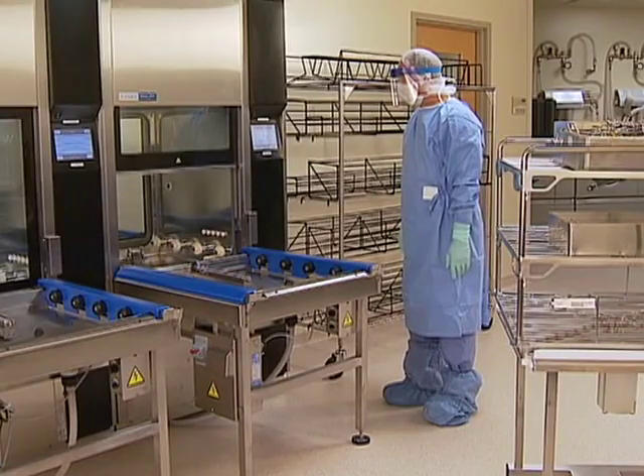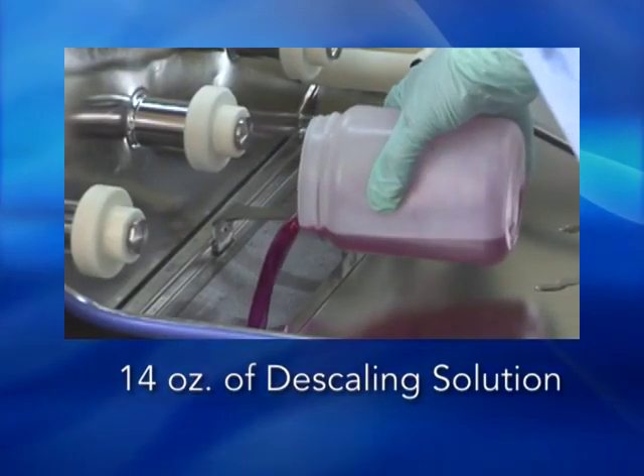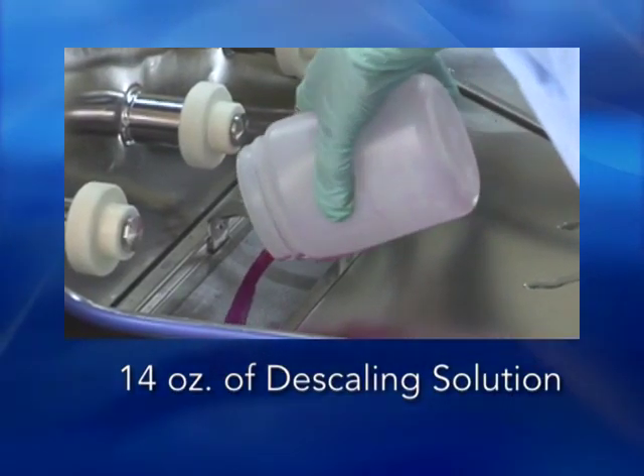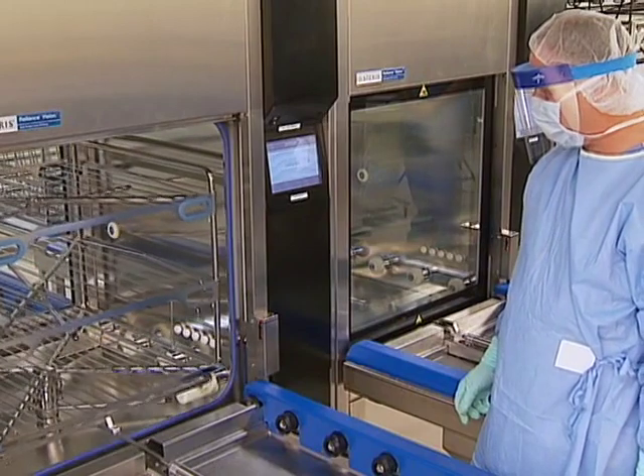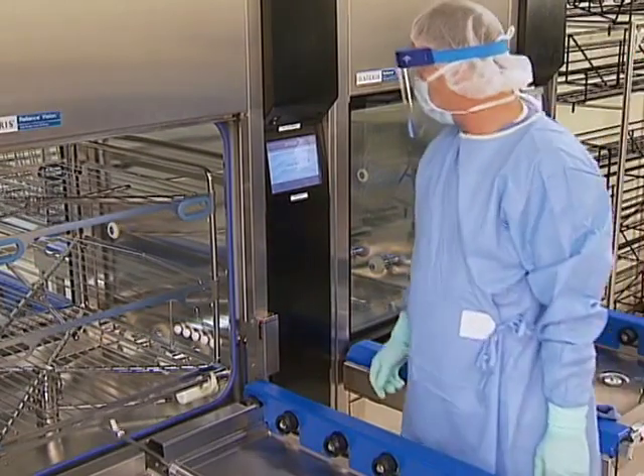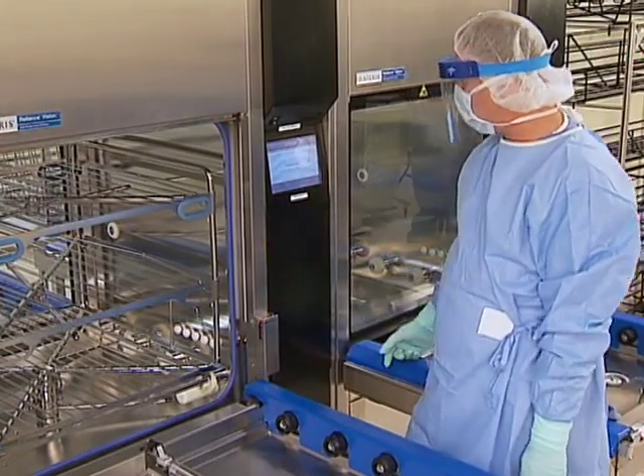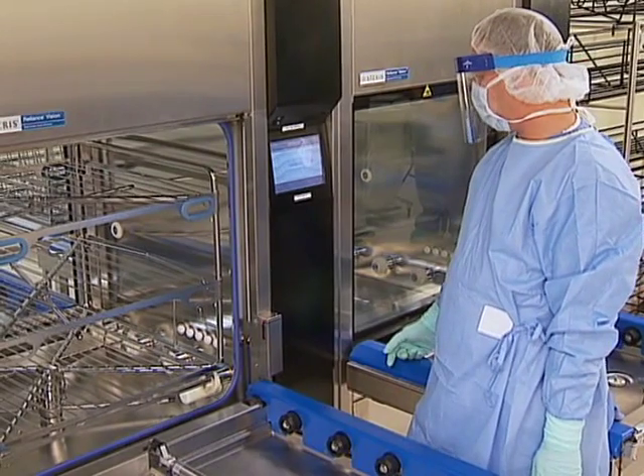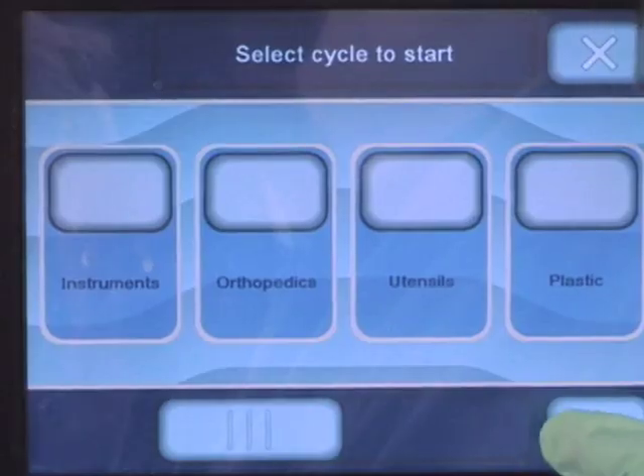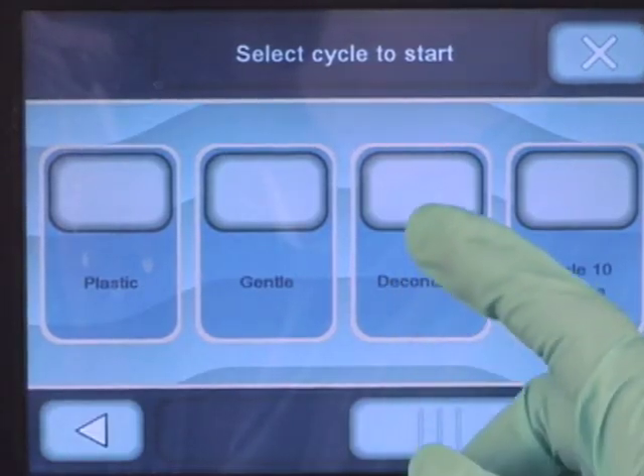First, open the chamber door and pour 14 ounces of descaling solution into the chamber sump. Next, load an empty manifold rack into the chamber. You can use a 2-level, 3-level, 4-level, or 5-level rack. Choose the decontam cycle on the control screen.